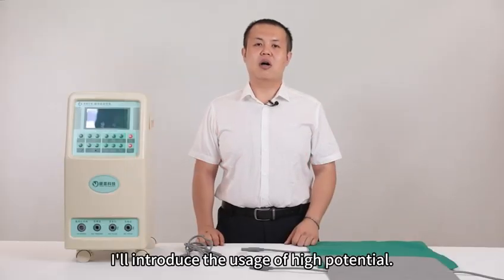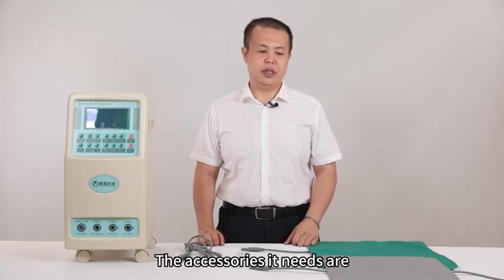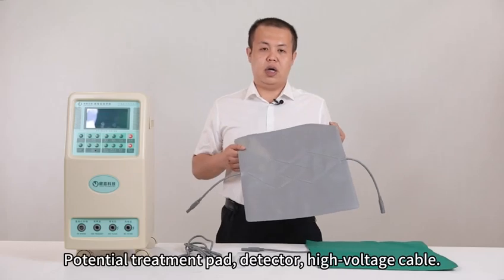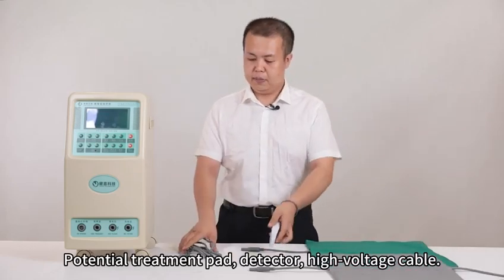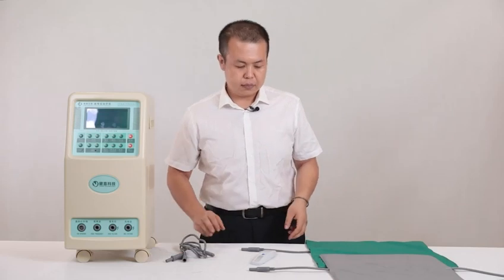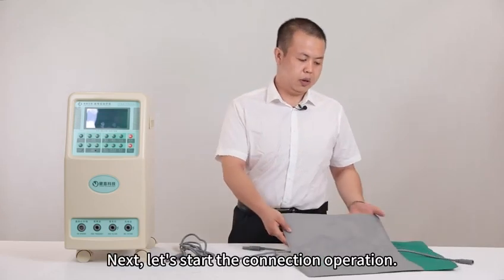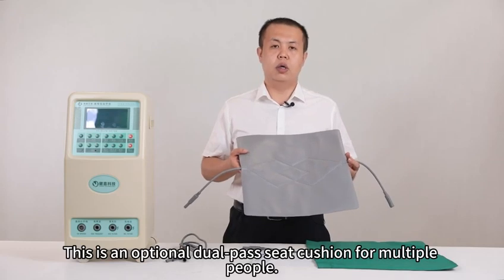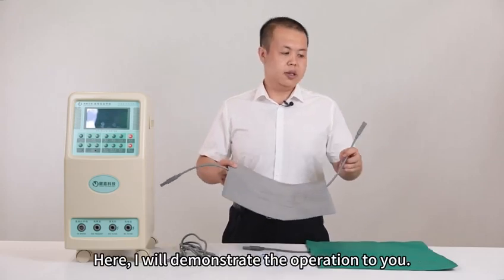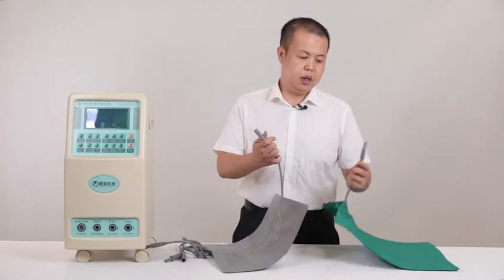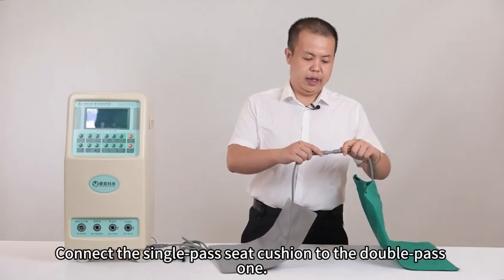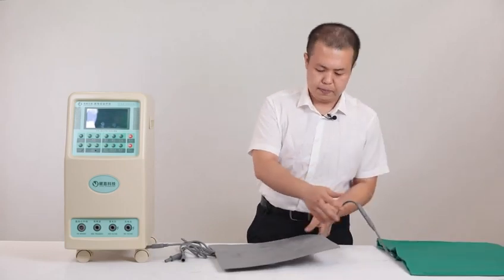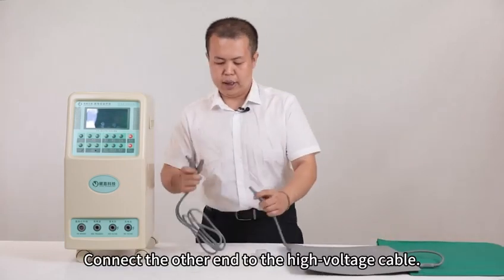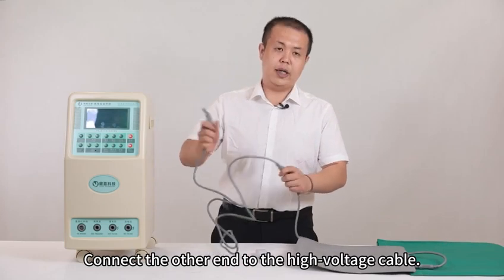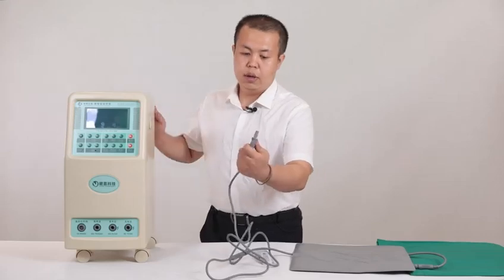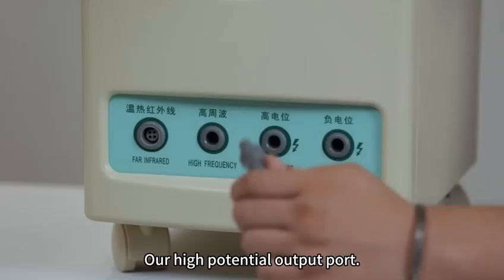The third function, I'll introduce the usage of high potential. The accessories it needs are potential treatment pad, detector, high voltage cable. Next, let's start the connection operation. This is an optional dual-pass seat cushion for multiple people. Here, I will demonstrate the operation to you. Connect the single-pass seat cushion to the double-pass one. Connect the other end to the high-voltage cable.